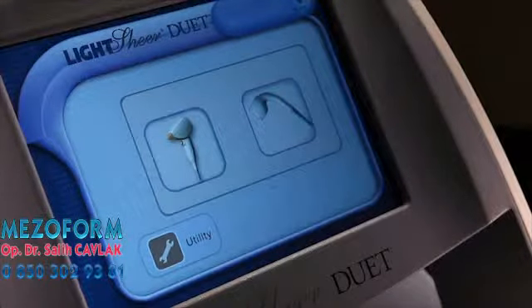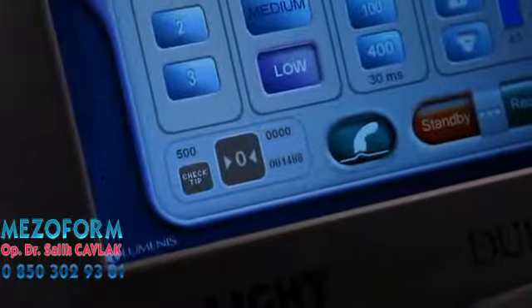The LightSheer Duet displays a unique treatment screen according to the handpiece you select. In the pulse counter field, the upper number displays the number of pulses delivered in the current session by the currently selected handpiece. The lower number displays the total number of pulses delivered by the selected handpiece. The tip counter registers the number of shots remaining before the LightSheer Duet suspends treatment and prompts the operator to inspect the handpiece tip. Clean the ET sapphire tip or replace the HS disposable tip if necessary.